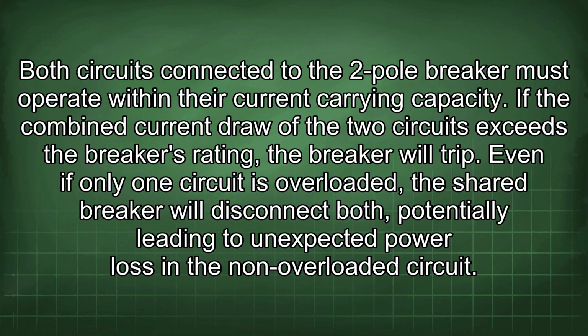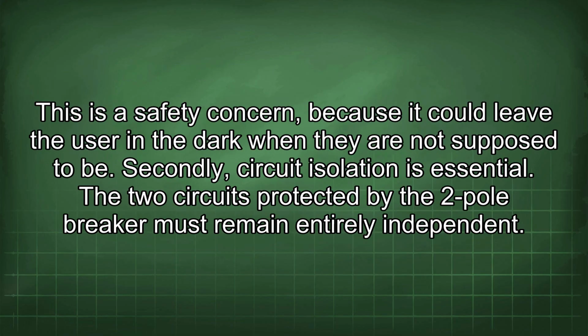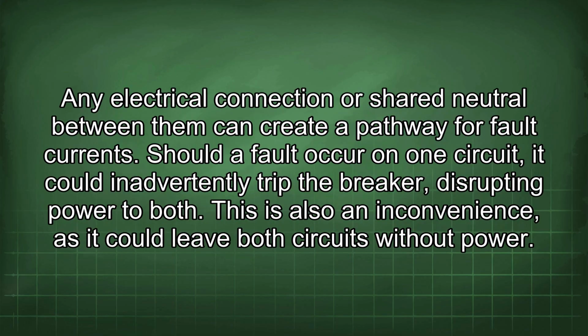Even if only one circuit is overloaded, the shared breaker will disconnect both, potentially leading to unexpected power loss in the non-overloaded circuit. This is a safety concern, because it could leave the user in the dark when they are not supposed to be. Secondly, circuit isolation is essential. The two circuits protected by the two-pole breaker must remain entirely independent. Any electrical connection or shared neutral between them can create a pathway for fault currents. Should a fault occur on one circuit, it could inadvertently trip the breaker, disrupting power to both. This is also an inconvenience, as it could leave both circuits without power.